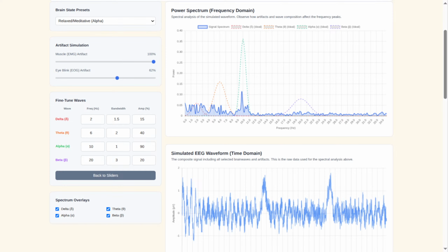That tells you how high the stakes are, how precise you need to be. And the details. Minimum 16 channels recording at once, specific electrode types like silver chloride, checking impedance, the electrical contact, making sure it's super low, ideally under 5K ohms. Right, because even a little bit of bad contact acts like static, drowning out those faint brain signals we need. And using that precise 10-20 system map for placing all 21 electrodes, ensuring everyone measures from the same spots.